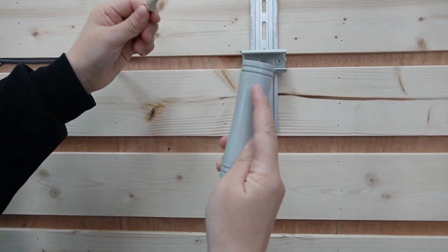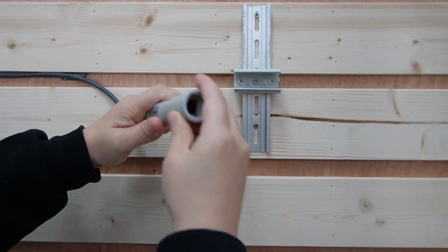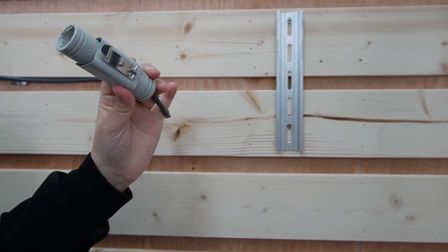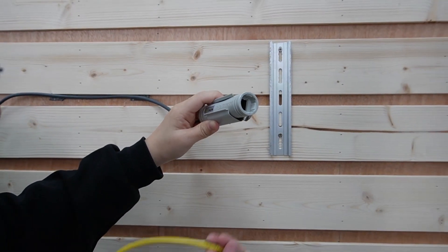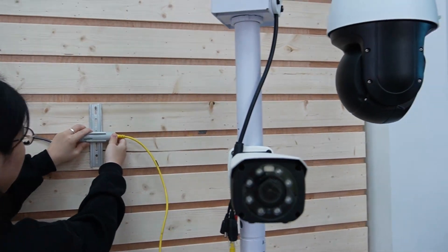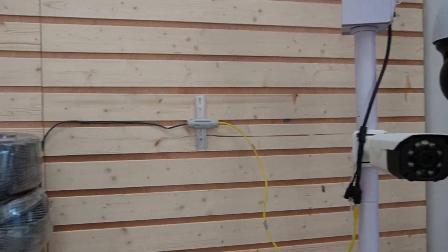First we have the input port — connect the 500-meter ethernet cable to the input port. Then mount it on here using this special mounting tool, which allows you to mount it on the DIN rail flexibly. Connect with the short patch cord that is already connected to the PTZ camera, and put it back on the DIN rail. Now we can hear the sound of the PTZ camera moving, which means it's getting both power and data at the same time.